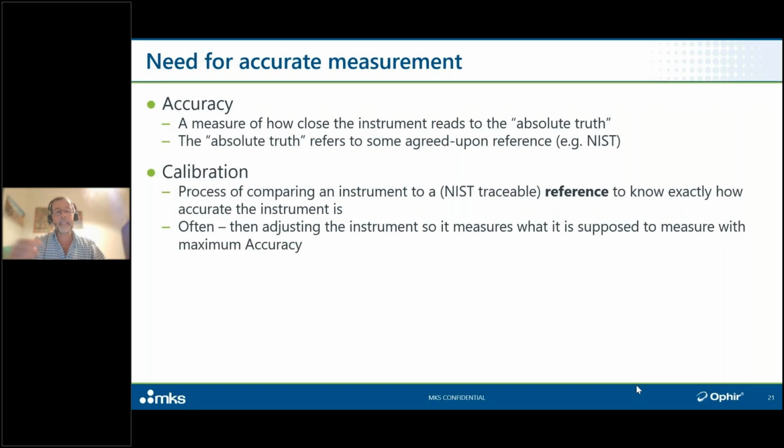What they mean is they're using a laser power meter, or a laser measurement instrument that they get from a manufacturer such as Ophir, to make sure that when their system thinks that it's driving their laser to produce 100 watts, it really is producing 100 watts. So strictly speaking, I don't know if that would be called calibration by a QA professional, but we all understand what we mean, so we're good.